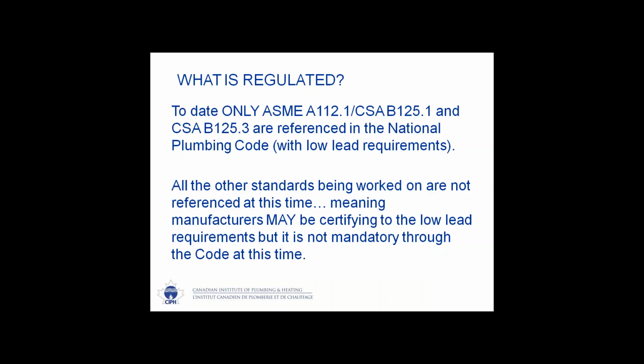With that being said, however, as Franco alluded to, when a standard is updated, a notification goes out to certification holders. And with that notification, they are required to update their certification records and be certified to the new requirements. And typically, they have a year or so. Franco, is that right? Yeah, typically about a year to be recertified to the new requirements. So while there may be a timeline yet for the National Plumbing Code to be updated with these new standards with the lead requirement, manufacturers will have to comply with many of these requirements for low lead because of the standards update. For instance, it's anticipated that B64 is going to be updated later this year, and that would mean that manufacturers would have to comply with those requirements probably by the end of 2016 or approximately. Franco?